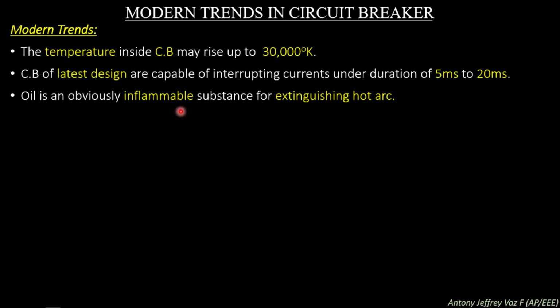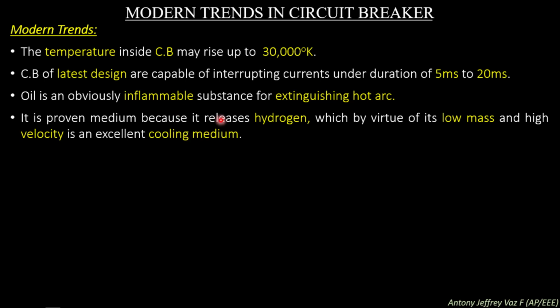We know oil circuit breakers are very good at this task and can be used, whereas we have a disadvantage in oil circuit breakers because oil is an inflammable material, so it cannot be used in consumer premises. It is a proven medium because it releases hydrogen, which by virtue of its low mass and high velocity is an excellent cooling medium. So hydrogen released from oil circuit breakers is used as the extinguishing medium, and it has a very low mass and a very high velocity, making it an excellent cooling medium.